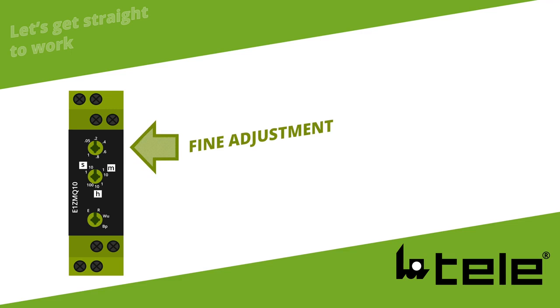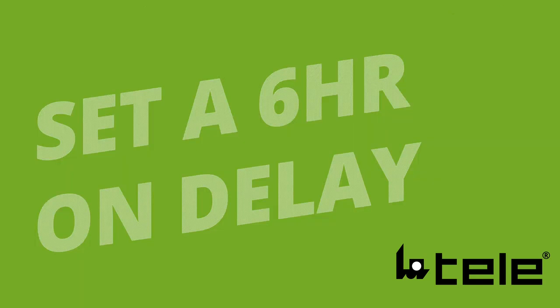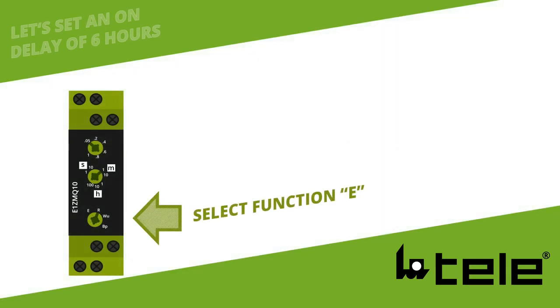Now, in order to adjust the time in a fine manner, you select a percentage of your end range on the top dial here. For example, if you have a 100-hour time delay and you set the top dial to 0.4, you get a percentage of that. Now let's look at how we can set a 6-hour on delay on our E1ZMQ10 timer relay, so you can get an idea of how this could work in real life.